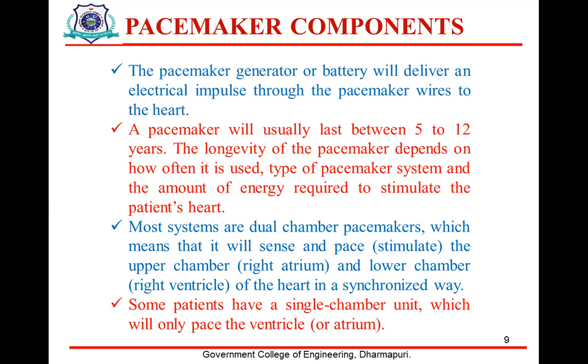A pacemaker will usually last between 5 to 12 years. This depends on how often it is used, the type of pacemaker system, and the amount of energy required to stimulate the patient's heart. Most systems are dual chamber pacemakers, which means they will sense and pace. It means they stimulate the upper chamber, the right atrium, and the lower chamber, the right ventricle of the heart, in a synchronized way. Some patients have a single chamber unit which will only pace the ventricle.